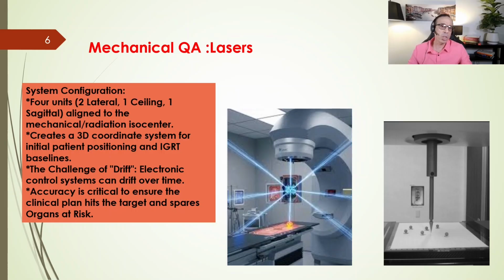It is important to remember that these aren't just light bulbs. They are sophisticated electronic systems. And like any electronic system, they are subject to drift over time. This is why we have strict daily tolerances to maintain. For non-IMRT machines, the daily tolerance is typically 2 millimeter. For SRS and SBRT machines, the margins are so tight that the tolerance drops to 1 millimeter.